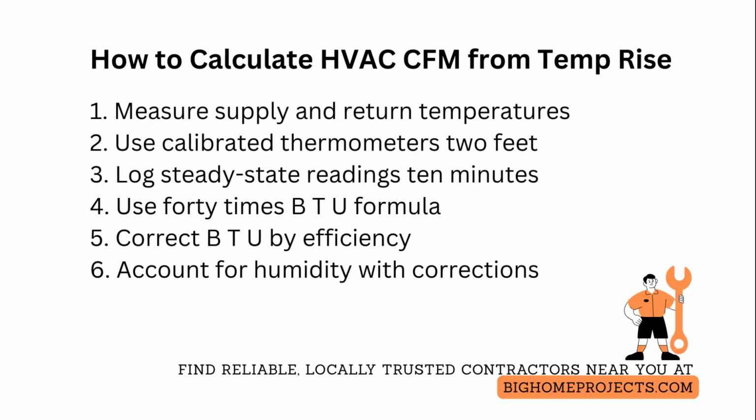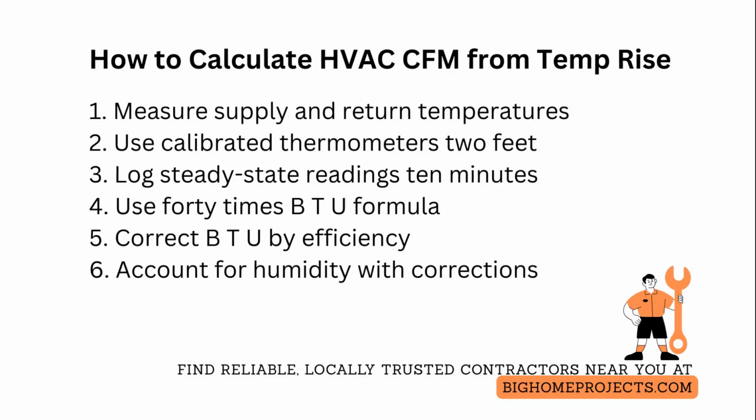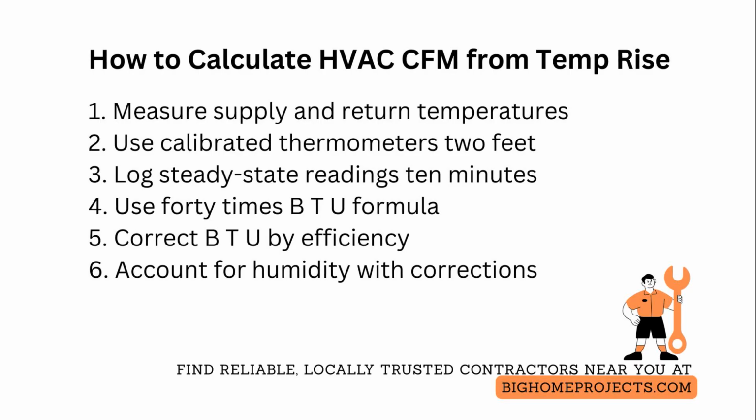Use the formula CFM equals 40 times BTU per hour divided by temperature rise, and always correct fuel input to delivered heat by multiplying by measured efficiency as a decimal to avoid overestimating airflow.